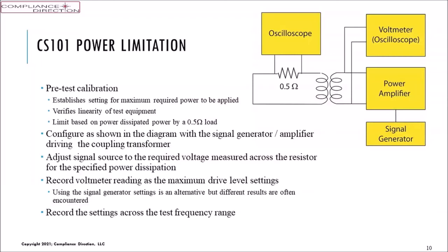Now, it doesn't say that we can't use something else, but what typically happens is we start overloading and causing distortion of the amplifier. Part of the calibration checks here are to verify that the waveform stays linear, stays sinusoidal. The sinusoidal waveform would indicate that we have limited distortion of our power amplifier, or we're maintaining the operation of the amplifier in its linear region. So we're operating it within its specified boundary conditions.